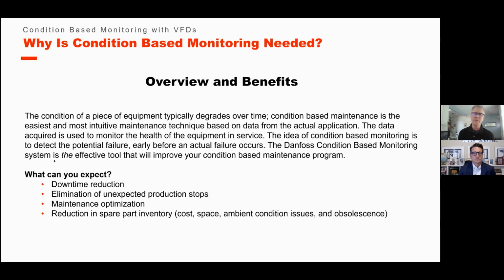There's a lot of ways to do this with a regular variable frequency drive, but not as accurate and not as early in the stage as with this software. It's very unique software, with the algorithms programmed into it. The Danfoss condition-based monitoring system is really that effective tool that will improve your condition-based maintenance program.